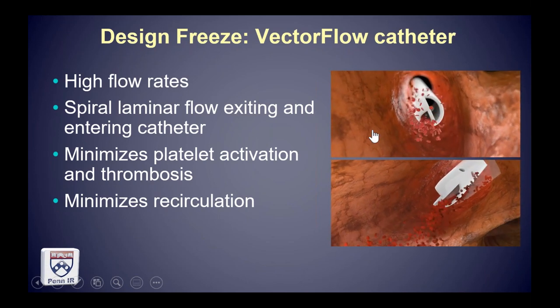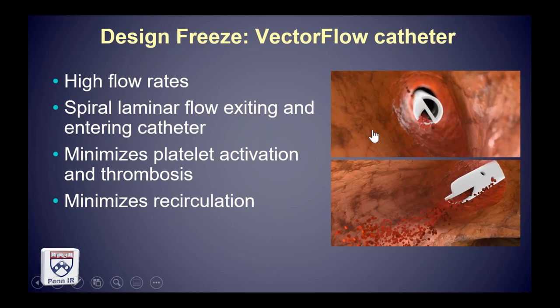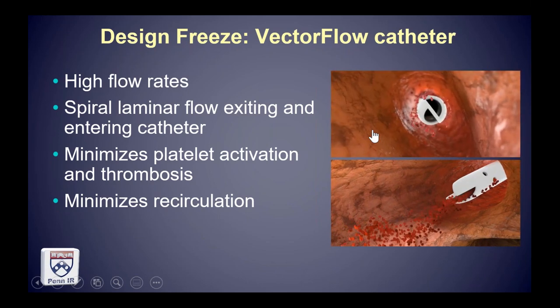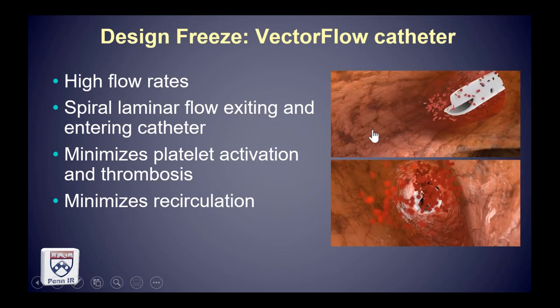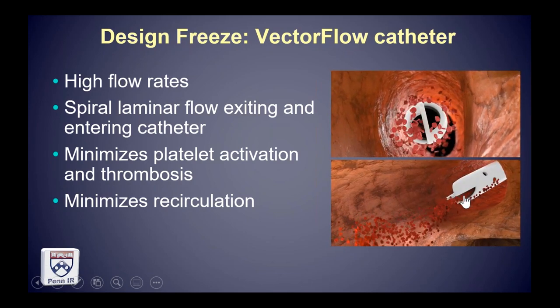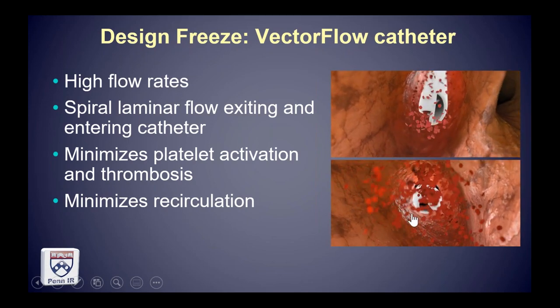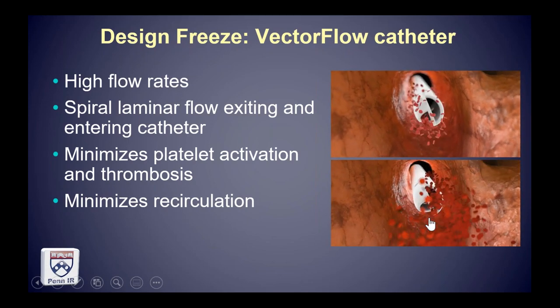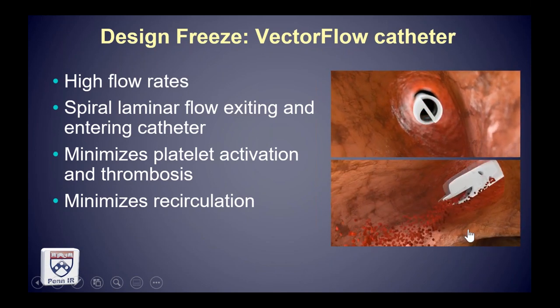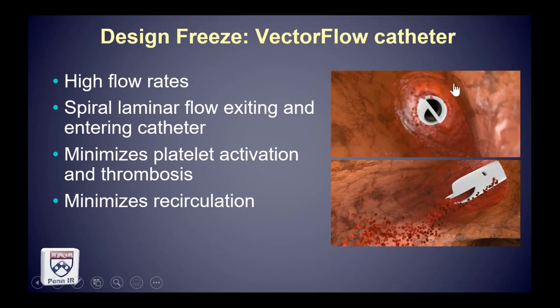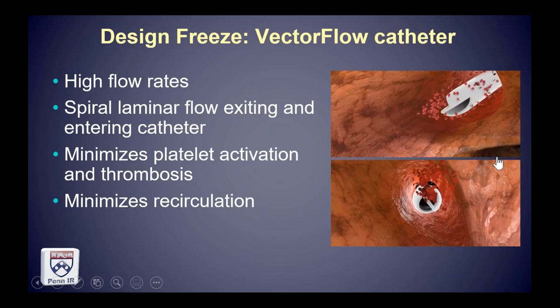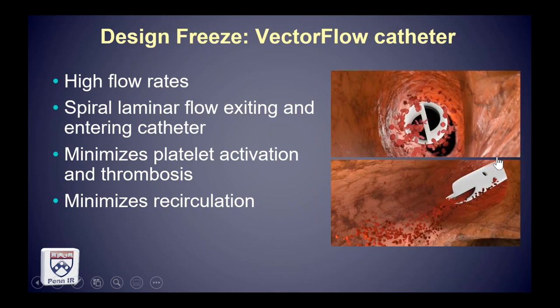At this point we had a catheter we'd spent years iterating to an optimal configuration. Literally one degree of difference in the helical-shaped tip deflects the flow enough to create a sufficient spiral laminar flow pattern, but not too much that it creates a so-called sidewall suck phenomenon that can occur when aspirating blood close to the superior vena cava. That was a highly iterative process — it took years.